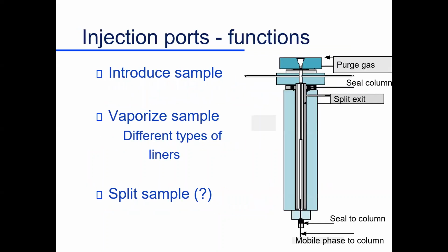So, flow regulators. Like I said, you have to get your sample into this gas. So we've got our carrier gas coming in, our mobile phase coming in. We've got to get our sample into that flow somehow so we can get our separation in our polymer. And that's done in what we call the injection port. So here comes our hydrogen. That's our mobile phase coming in. The hydrogen comes into what we call the injection port. This is a heated chamber. We'll typically run 250 degrees centigrade.